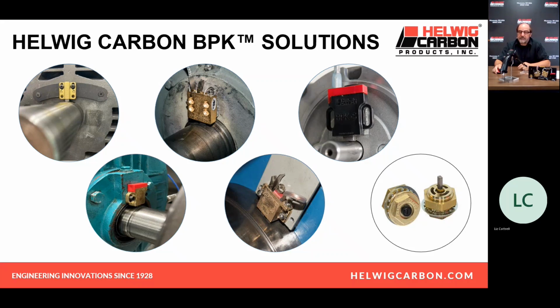Here you see examples of bearing protection kits mounted on a variety of motors. Remember, we not only come at the shaft radially with pre-made brackets for your motor, so you can just simply loosen bolts, put our kit on, tighten the bolts back down. No pulling apart, no decoupling your motor from your downstream equipment, installing, drilling, tapping, reassembling, realignment. We don't have to do any of that with our stuff. If you can't get at the motor shaft, we also make a variety of axially mounted kits, so we can come at the shaft axially instead of radially.